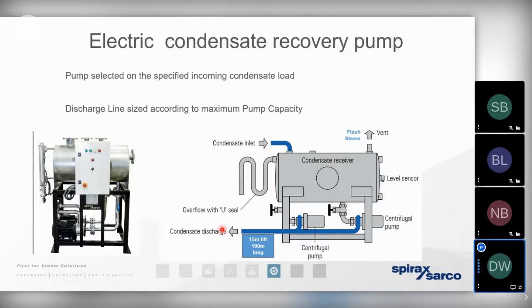So if we were working in the boiler house and we saw that temperature gauge hanging at significantly less than 80 degrees, we could run the calculation to determine how much condensate was coming back to the boiler house. And then the first thing we should do is visit the plant room where one of these receivers was located to identify where that condensate was actually going. Typically, it would be as a result of the centrifugal pumps failing.